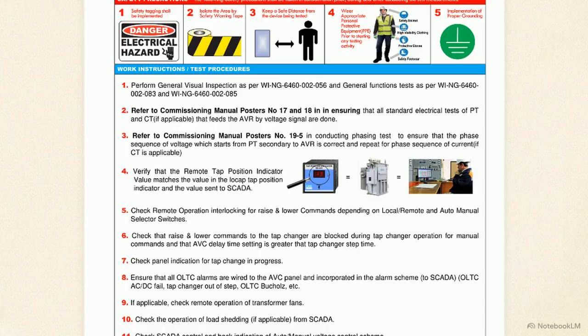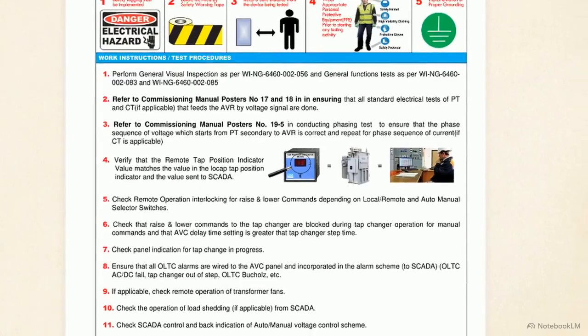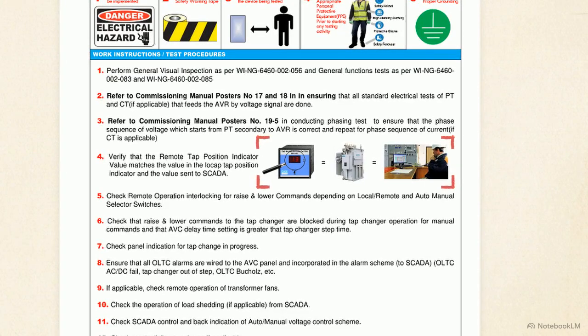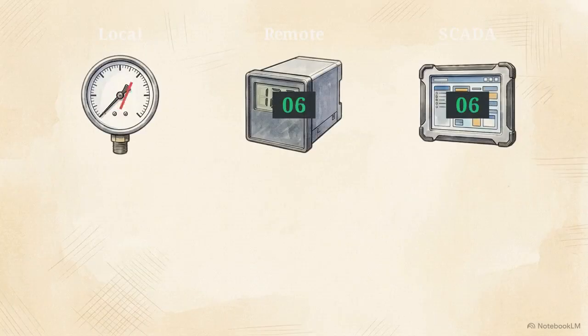The first procedural module focuses on verifying the control panel scheme, the tap position, and SCADA feedback. We begin by checking the alignment between the remote tap position indicator, the local tap indicator, and the SCADA feedback screen. For any given transformer tap position, the values at these three separate locations must match perfectly.